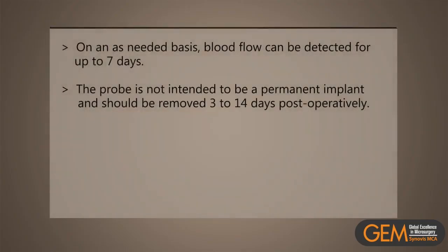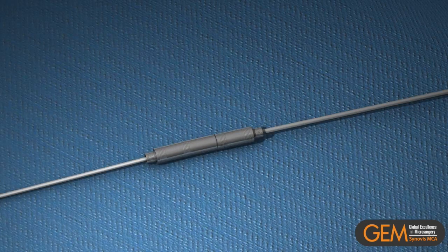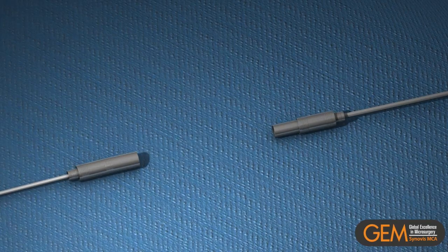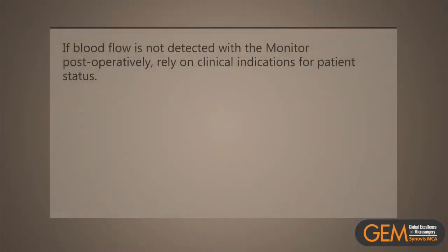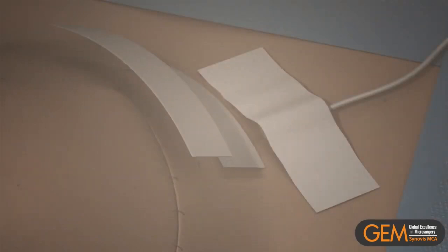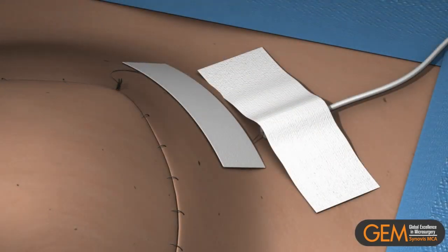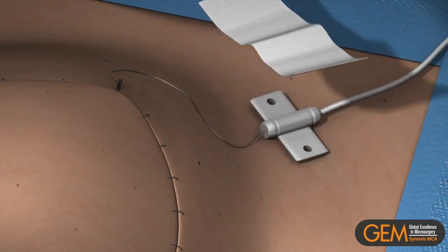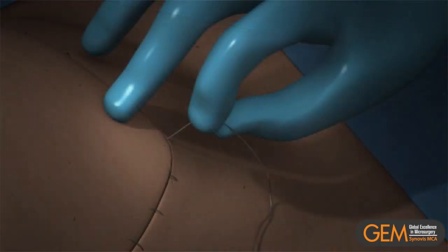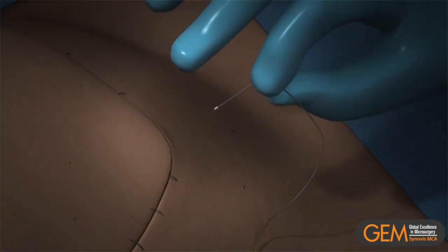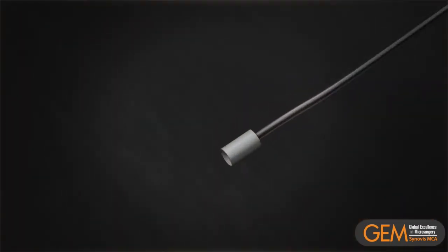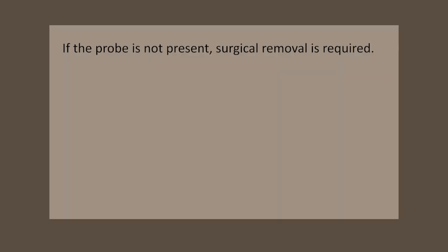Blood flow can be detected for up to 7 days as needed. The probe is not intended to be a permanent implant and should be removed 3 to 14 days postoperatively. When monitoring is not performed to detect blood flow, the external lead may be disconnected from the probe by pulling the probe connectors apart. If blood flow is not detected with the monitor postoperatively, rely on clinical indications for patient status. To remove the probe, first detach the suture sleeve and wire from the skin by removing the suture, tape, or staple. Remove the probe by applying gentle traction to the wire at the site of the incision until the probe is extracted. With visual inspection, confirm that the probe is fully intact. If the probe is not present, surgical removal is required.